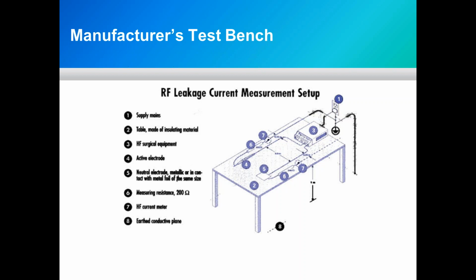60601-2-2 test standard, because for a manufacturer, they cannot exceed 150 milliamps of leakage current on single fault condition on any of the energy ports. Now, as a manufacturer, they can define something less than 150 milliamps. There are some manufacturers that for a certain output port will specify 69 milliamps as pass-fail. This is always done with a fixed 200 ohm resistor. On the Uni-Therm, we have those located on the side of the unit. They're independent resistors, not attached to our load resistor, or load resistance bank, I should say. And again, the limit is 150 milliamps.